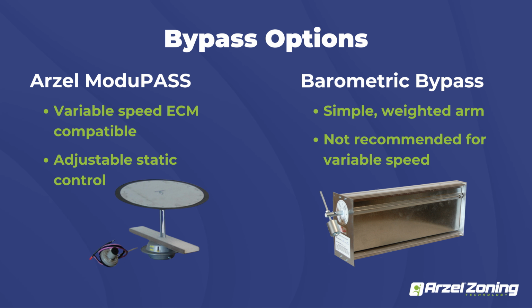We have our barometric bypass. Sure, you guys are all familiar with it. It's got the weighted arm. You adjust your weight, and that's going to open based on the static pressure in the system. Works really good for basically 3 zones or less, as long as your zones are kind of evenly sized. But if you guys are getting into anything really more than 3 zones or dramatically different size zones on a job, or if you guys are doing variable speed or ECM equipment, which is going to be most of the new equipment nowadays, you're going to want to steer away from the barometrics.